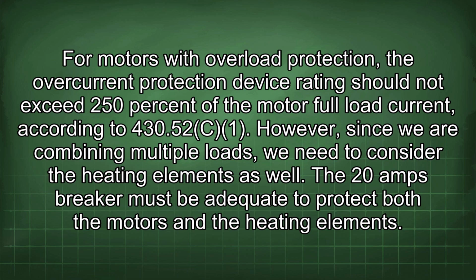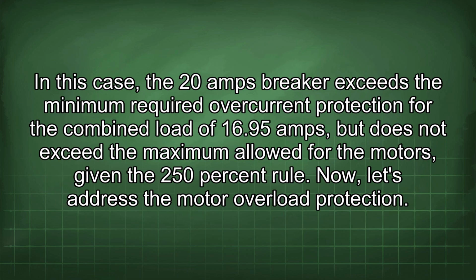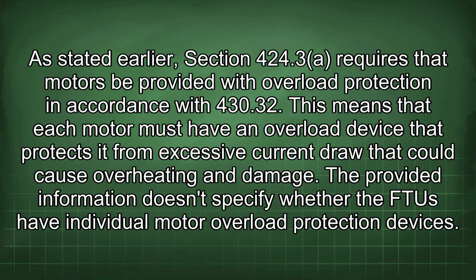The 20 amp breaker must be adequate to protect both the motors and the heating elements. In this case, the 20 amp breaker exceeds the minimum required overcurrent protection for the combined load of 16.95 amps, but does not exceed the maximum allowed for the motors, given the 250% rule. Now let's address the motor overload protection.